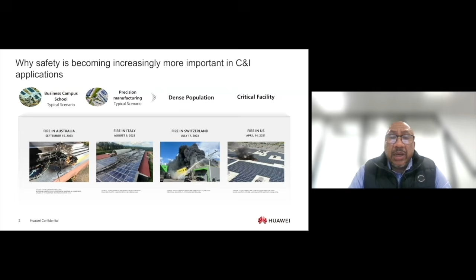What we have found in past research is that where incidents do take place, noting that they are quite rare, they are mostly related to issues on the DC side of installations, where we typically find a PV-to-ground problem, and also quite a high PV current or inrush current issue. That relates to the higher energy density we've seen within the power plants that have been implemented, in this case solar PV, with much higher energy density as well as a higher likelihood of DC faults.